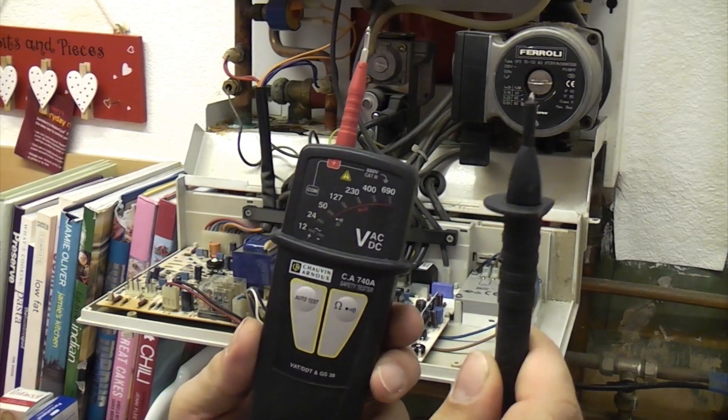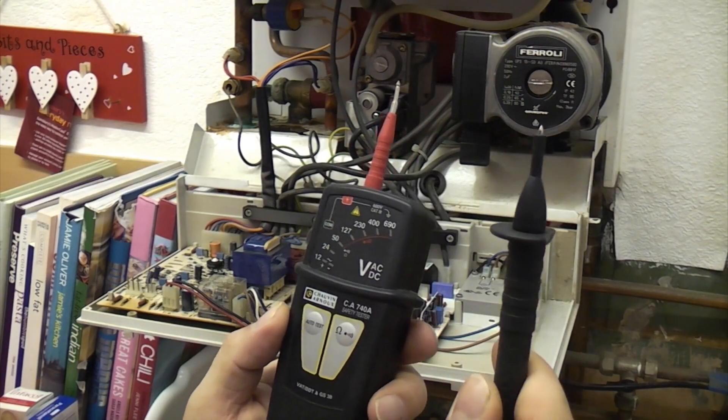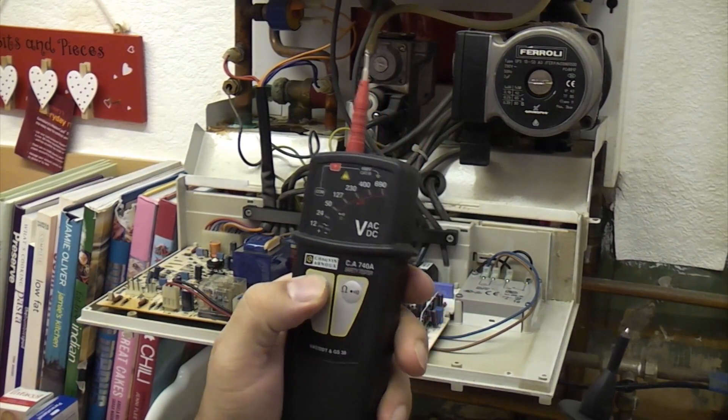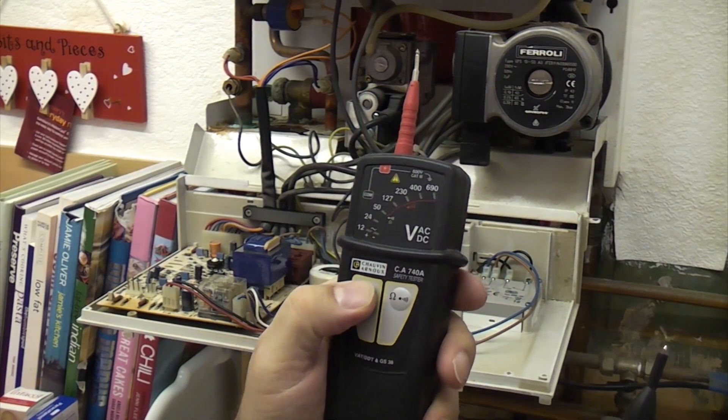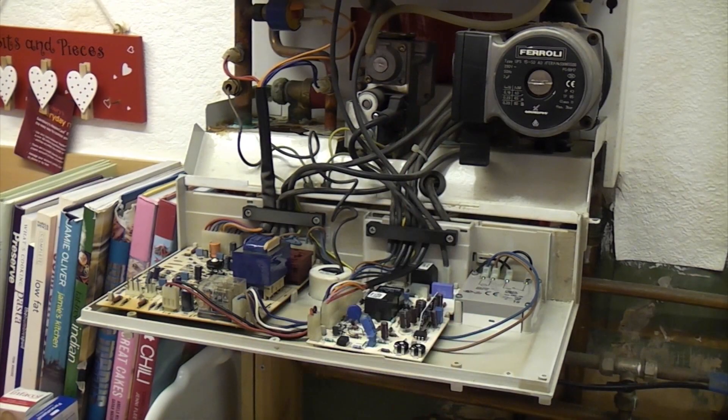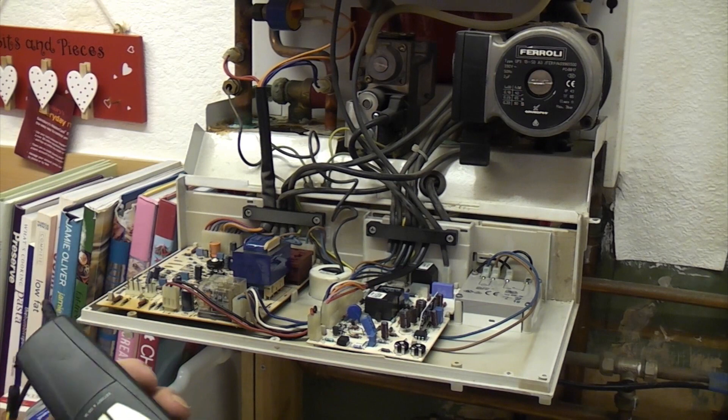And then before we do anything else, we are just going to get our approved voltage checker, and we are just going to test its working by pressing the test button, and then we are just going to check a couple of places on the boiler to ensure that it is completely dead.